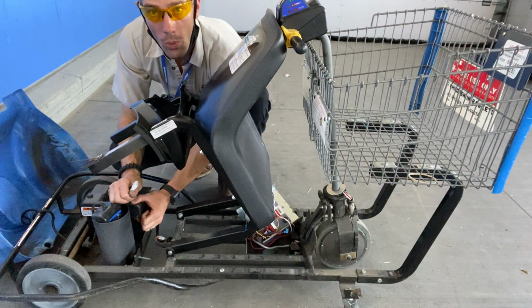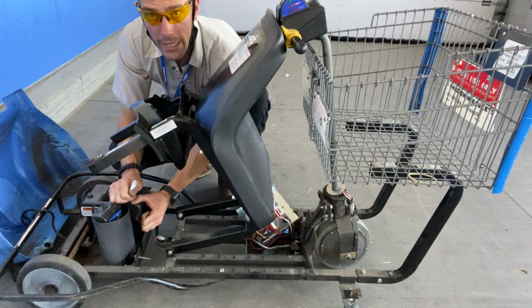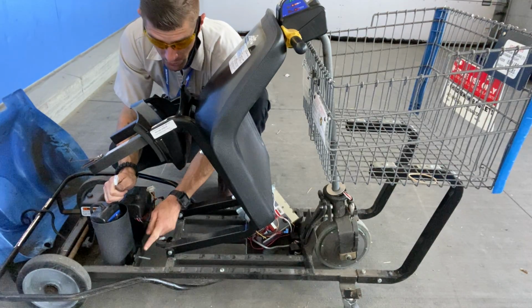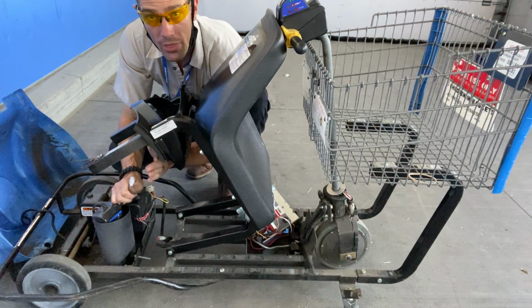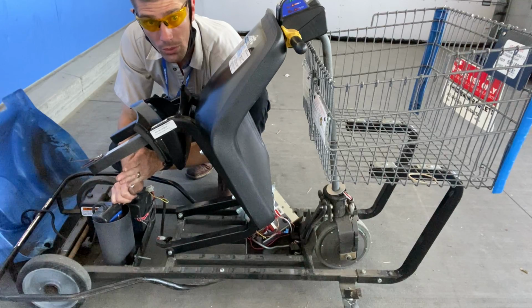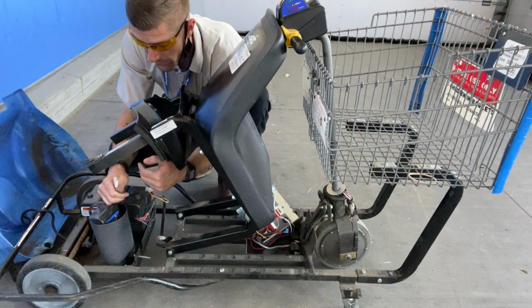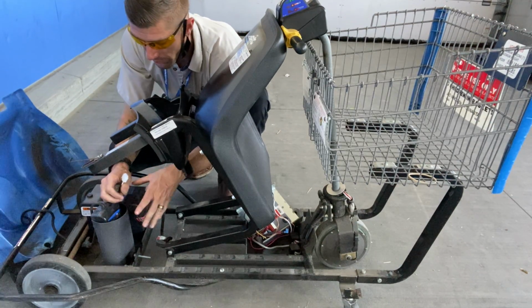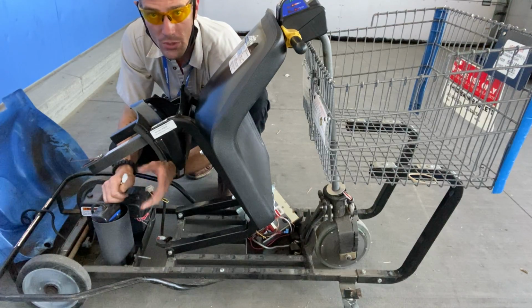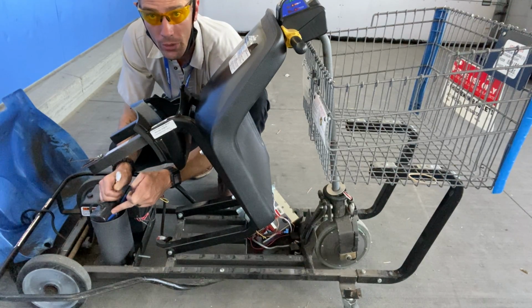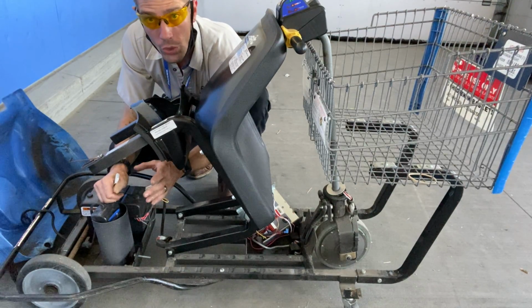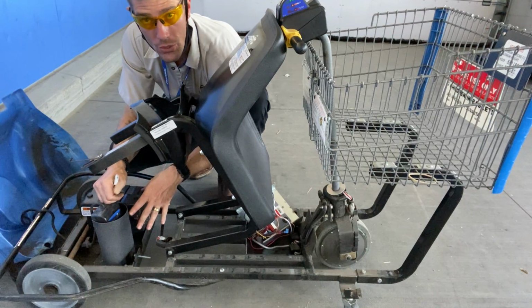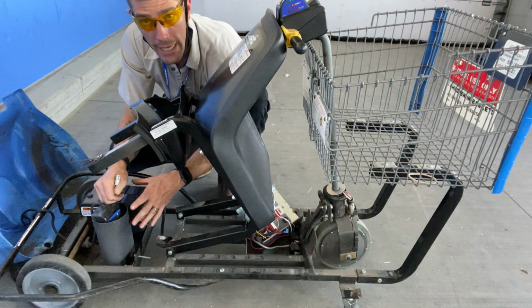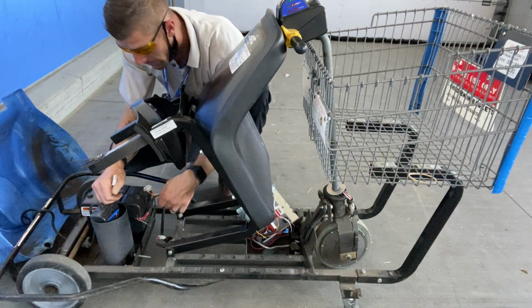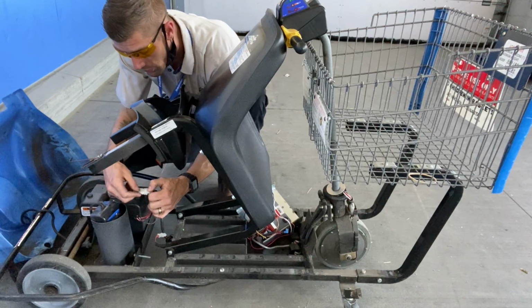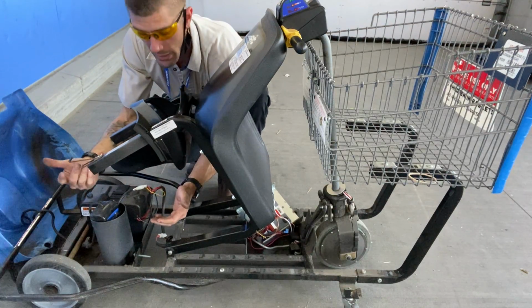The battery is 12 volts. Your rating of the battery output or the charger output should be between 13 and 14 volts, 1 or 2 volts higher depending on the charge level of the battery, and some of them are smart. This is a 10 amp charger. It's very important that when you get replacement batteries for this unit, they can withstand 10 amps worth of charging. It's meant to be a rapid charge so there's low turnover time for customers.